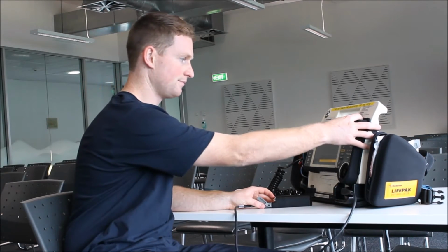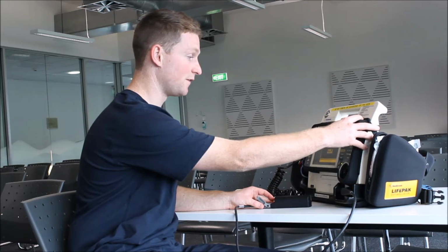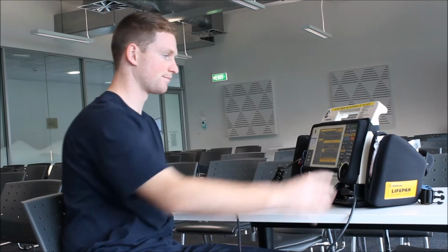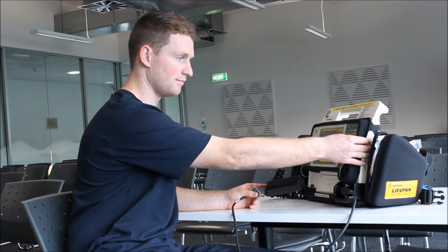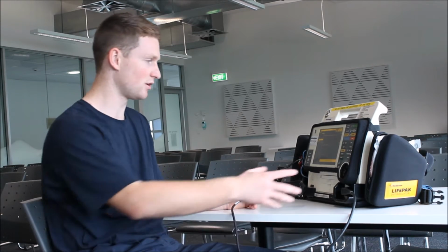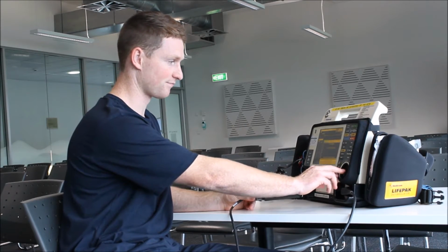Go into advisory. Select our energy, because it's only a test, we'll go down to 50 joules. Charge it up. That's just the noise of it charging. And then administering a shock. Now it's delivered a shock, now we're going to test that you can disarm the shock. We do the same thing again, down to 50 joules, charge it up. But this time I'm going to press the selector knob to cancel it. There you go, so that's disarming that charge.